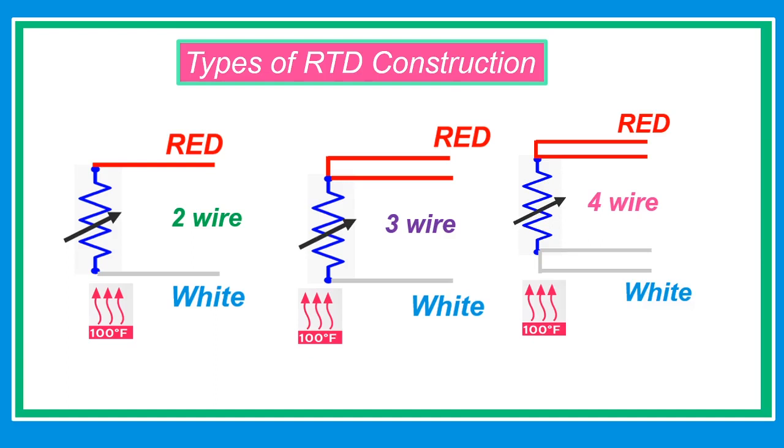In the four-wire configuration, two lead wires are connected to either end of the RTD. In this configuration, the RTD resistance may be measured with a four-wire resistive measurement with superior accuracy. Four-wire RTDs yield the most accurate measurement but are the most expensive RTD configuration.